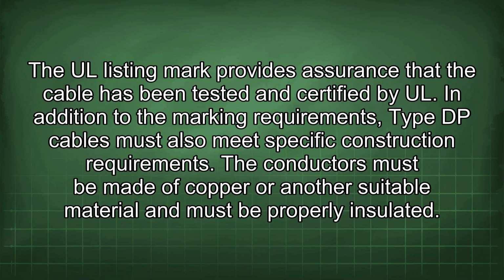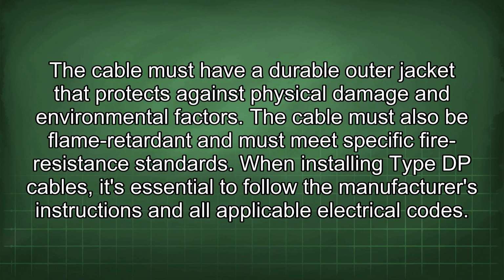In addition to the marking requirements, Type DP cables must also meet specific construction requirements. The conductors must be made of copper or another suitable material and must be properly insulated. The cable must have a durable outer jacket that protects against physical damage and environmental factors. The cable must also be flame retardant and must meet specific fire resistance standards.